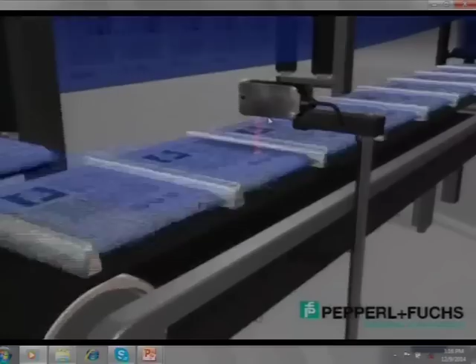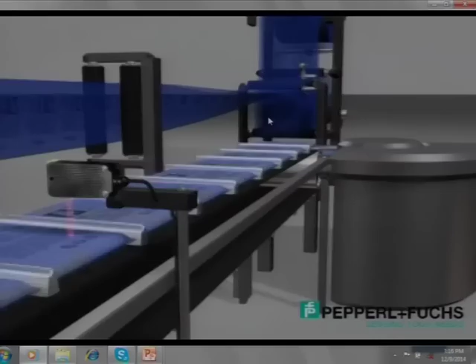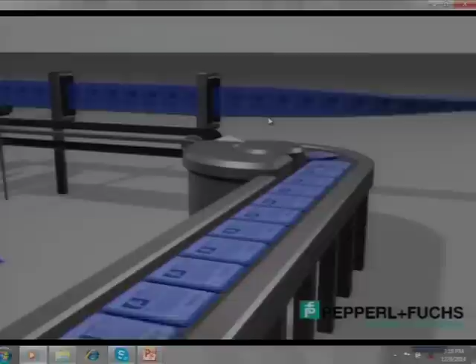This is for empty pouch detection, right? If there is air or anything, it can get detected. Again, this is a background suppression sensor that is not supposed to sense the background, it is only sensing the back on the top. So this was just a video showing how inductive, photo, ultrasonic and capacitive sensors are used together in this machine, which is known as an FFS machine, form, fill and seal machine.